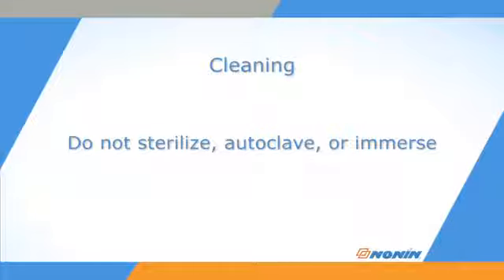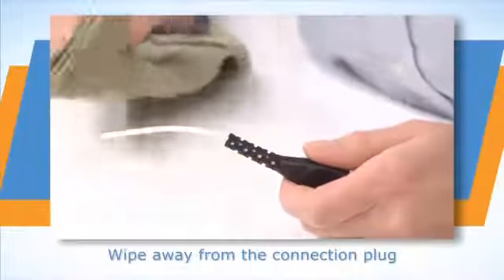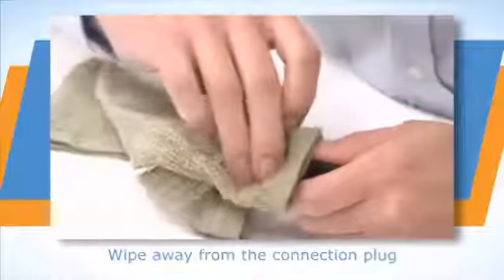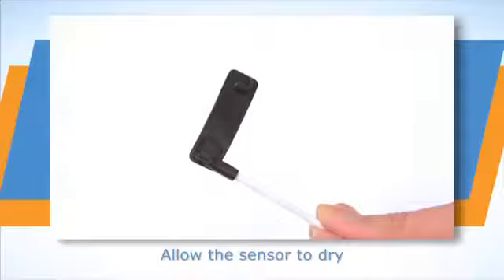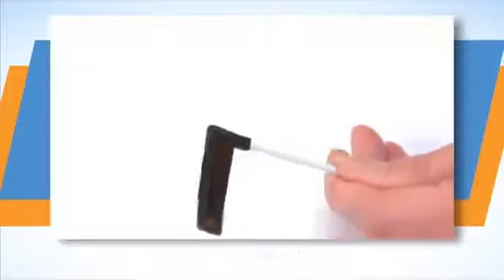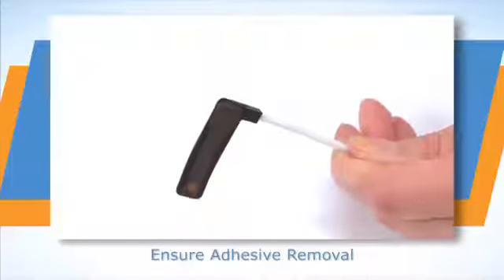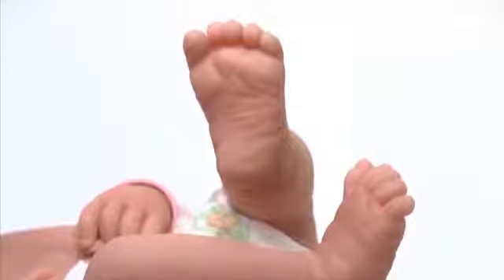Do not pour or spray any liquids onto the sensor. Wipe away from the plug on the cable toward the sensor. Allow the sensor to completely dry and check that all adhesive from the previous use has been removed before the next application. You may rotate to the other foot on the patient to maintain skin integrity and patient comfort.